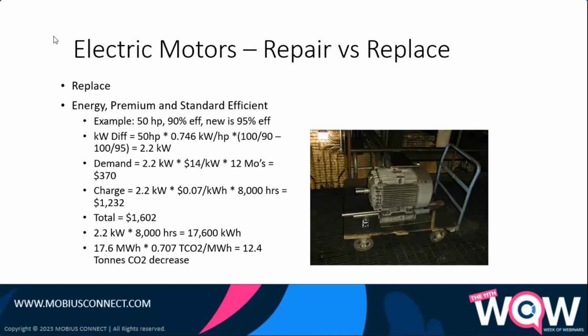So that would be on average in the United States 0.707 metric tons, and there are 2,240 pounds per metric ton. So it's 0.707 times 17.6 megawatt hours, so it'd be 17,600 kilowatt hours divided by 1,000. And that gives me 12.4 tons of CO2 decreased by going to a premium efficient piece of equipment.